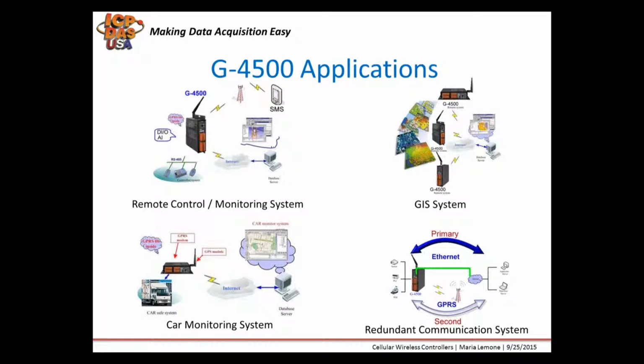In GIS systems, G4500 passes on geological information including river levels, water chemical measurements, and other information back to a SCADA system for analysis. Alarms are triggered when the measurements are outside of safe levels. In redundant communication systems, I/O modules are connected to G4500 over the RS485 bus, and the status of the I/O can be seen from a remote location. Communication is established over the Internet via both Ethernet and cellular as needed. If the Ethernet pathway is down, communication is sent across the cellular network to make sure the information can get across.